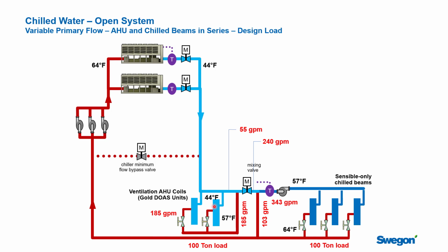But this is the part where you need to stop, look at your building, and think through how it's going to behave in different seasons to make sure you don't get surprised, right? Because this flow comes down, goes through here, it's in series, and comes around through this mixing valve in here, where we're going to modulate how much of this is coming down here and being mixed with this. And so that rule about saying, hey, this flow rate always has to be greater than this flow rate is just to get the system to behave well from a flow rate point of view, not from a temperature point of view.